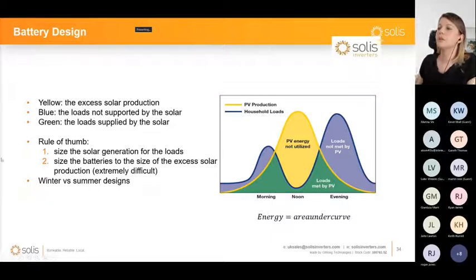So the rule of thumb is to size the solar generation for the loads in order to cover the loads, and size the batteries to cover that excess of solar production, which of course is really difficult to estimate, but for each type of household there are some baselines that you can follow. And you have to make sure that when you are doing the design, you can do a winter design and a summer design.